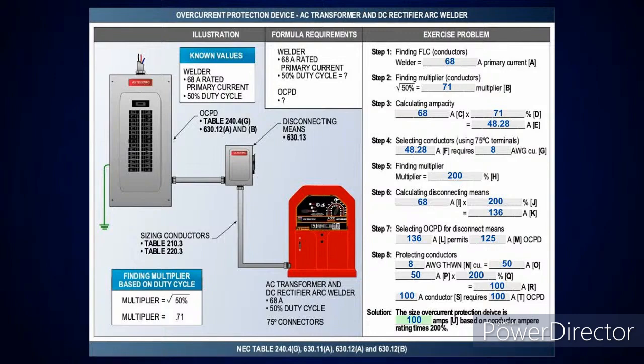So that means I'm going to drop down, which falls into that rule of thumb once again if I'm above 125%. So I take the 68 amps at 200%. That gives me 136 amps. The next size below that is a 125 amp overcurrent protection device. Now I'm going to cross check this and see if I can protect the conductors at a lower rating, so you could say putting 100 amp instead of 125 amp here. If I take the 50 amp conductors at 200%, that gives me 100 amps, which is a 100 amp overcurrent protection device. Okay, so there's 2 ways to do it. Or I could just take 68 amps at 200% and put a 125 amp overcurrent device on it. I could do it that way also.